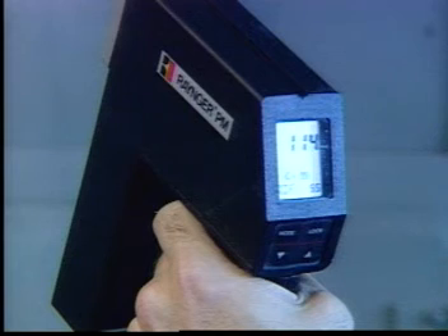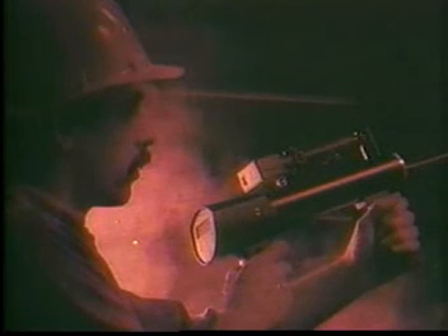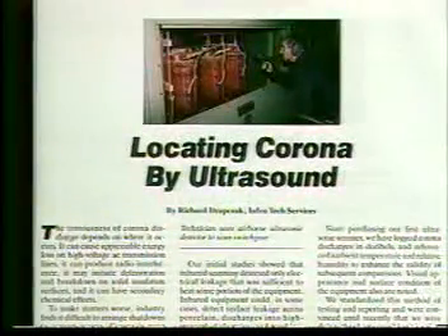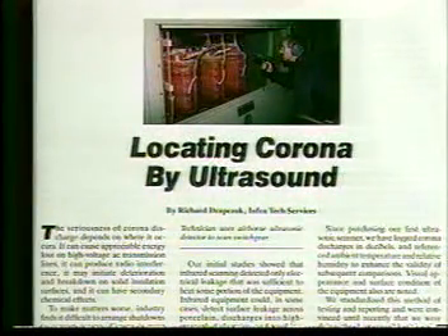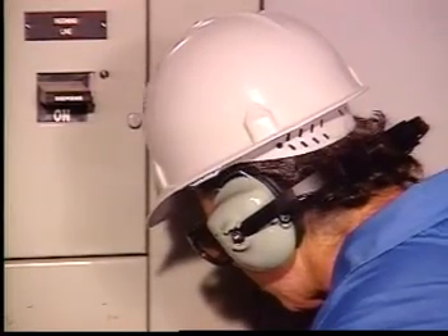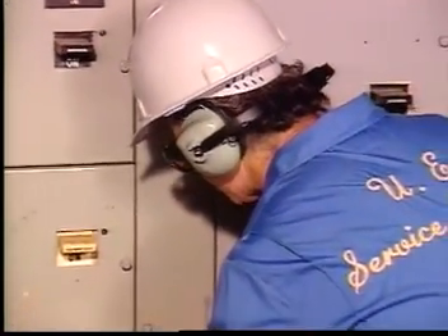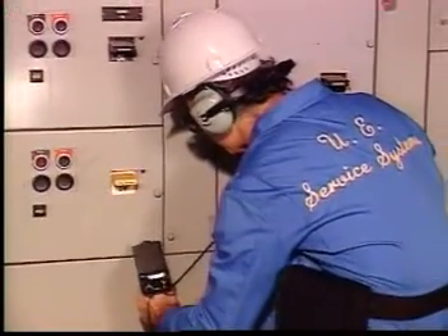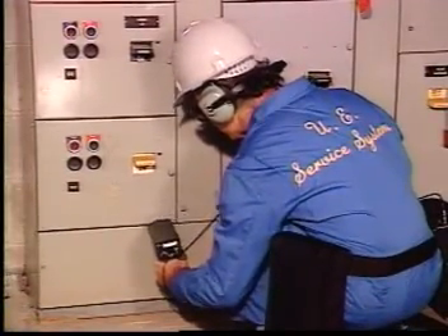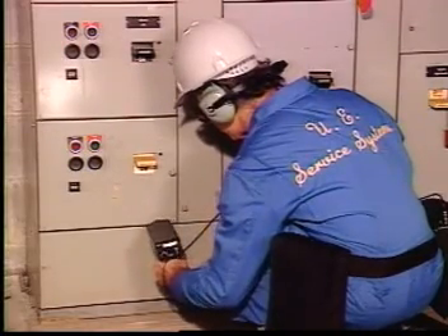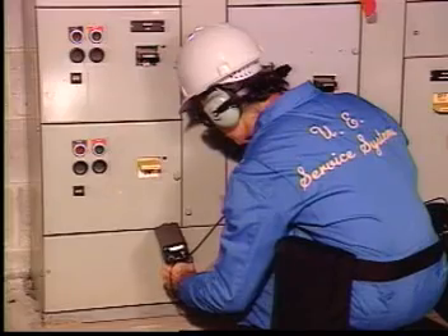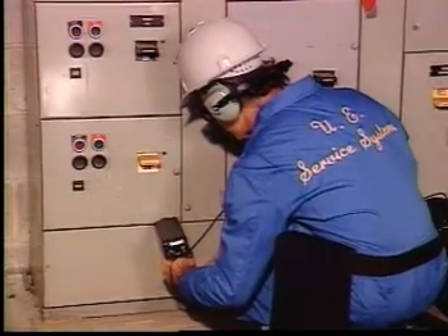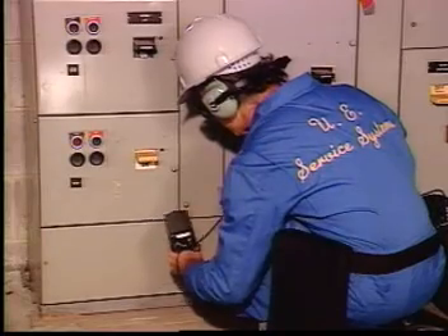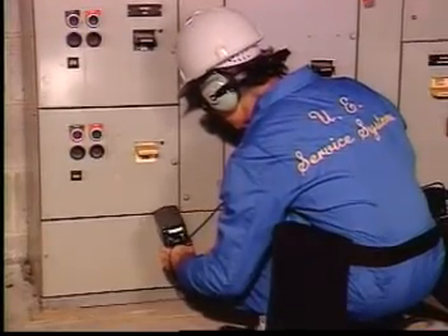Ultrasound works well when used in conjunction with other technologies, especially with infrared testing. As one ultraprobe user explained, infrared inspections allow operators to see light the eye cannot see, and ultrasound allows them to hear sounds the ear cannot hear. This is particularly important where surface temperatures may mask infrared detection of an underlying problem. Sound waves pass through any tiny crevice and are readily picked up with the ultraprobe. A switchgear enclosure can be tested using ultrasound without opening the door and shutting down power. By scanning around the seal of the door, sounds of discharge can be detected.